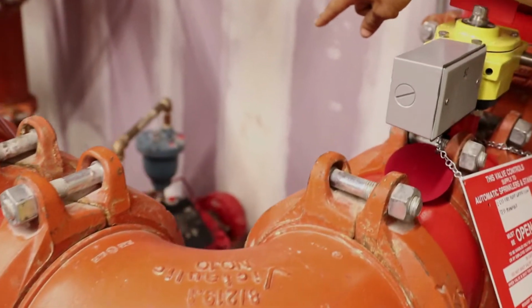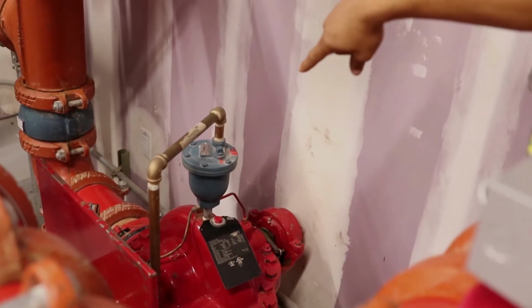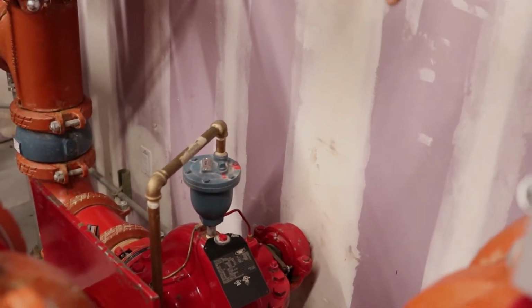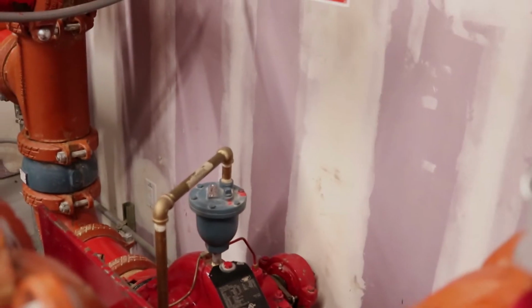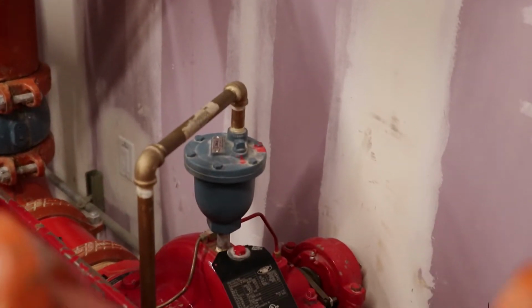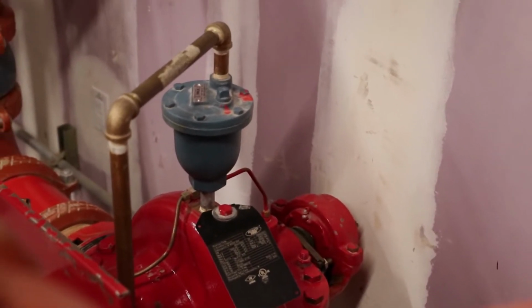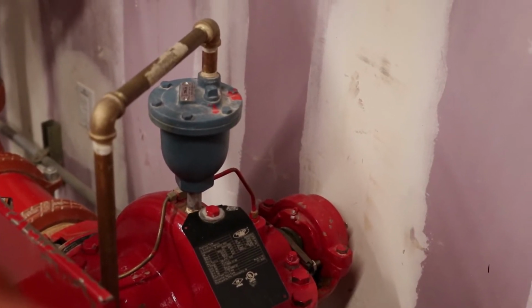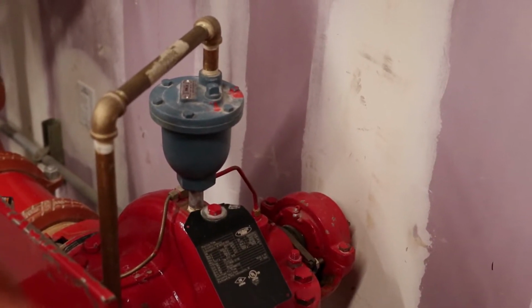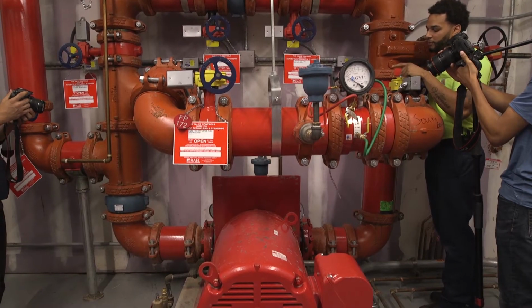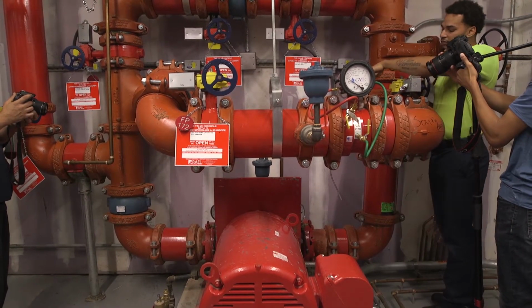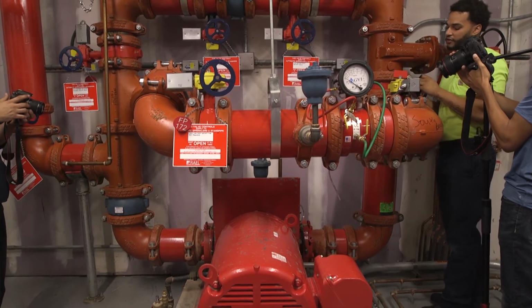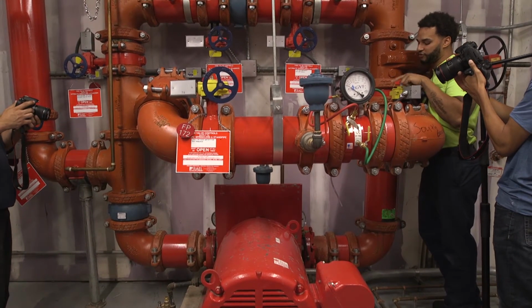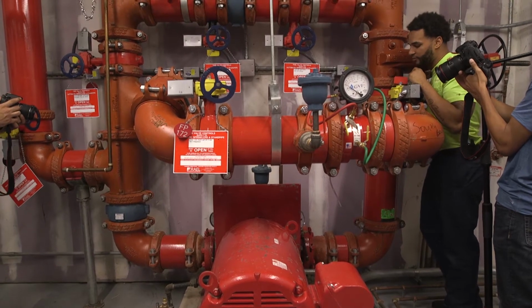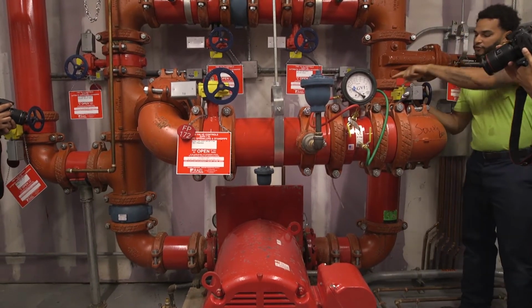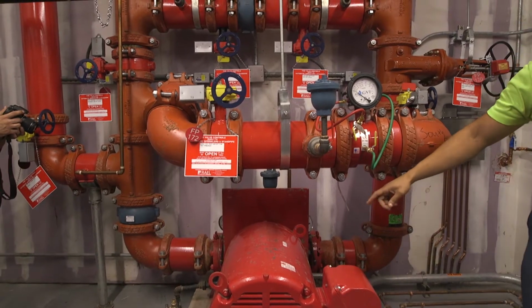Now if we look at the top of that fire pump, that blue valve on the top is called our air relief valve. When this fire pump first operates, we start creating water disturbance and turbulence. That starts creating air pockets when the fire pump operates. To prevent those air pockets from making our pump airbound, that air relief valve is going to discharge any of that air that travels into the system and just dump it from right there. Now if we go over to the discharge side, we're looking at the discharge side pressure gauge here.